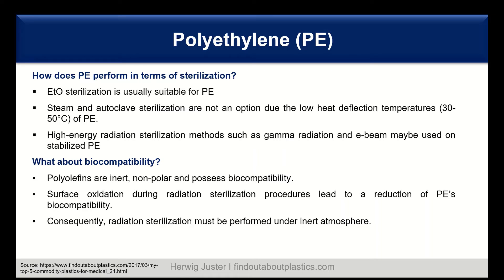High energy radiation sterilization methods such as gamma radiation and E-beam may be used with stabilized polyethylene. Regarding biocompatibility, polyolefins in general are inert, non-polar, and possess biocompatibility. However, surface oxidation can occur during radiation, which leads to a reduction of biocompatibility. As a consequence, when radiation sterilization is applied, it must always be performed under an inert atmosphere.